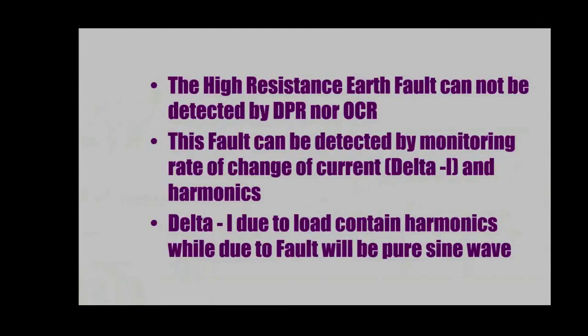High resistance earth fault cannot be detected by the distance protection relay nor the overcurrent relay. DPR means distance protection relay. OCR means overcurrent relay. When there is a high resistance, what do we see? Ohm's law. Z is equal to V by I. So I is equal to V by Z. If your impedance resistance is very high, Z is very high, your current will be very low because they are inversely proportional. So when the current is very low, your distance protection relay will not pick up. And the overcurrent relay also will not pick up because the current is low. So in this kind of situation, these two relays cannot identify the fault. Therefore, the backup is delta I.